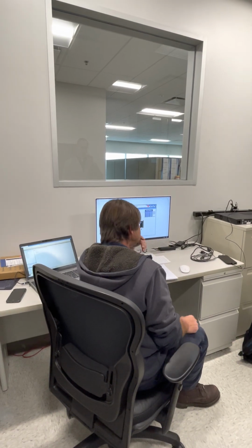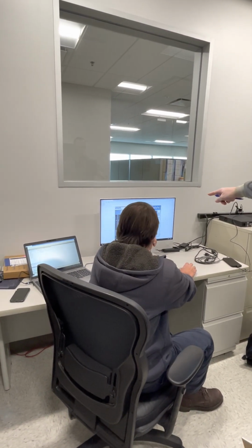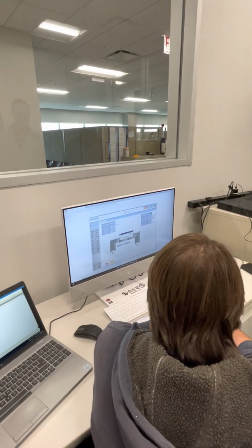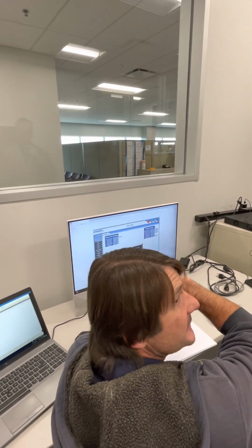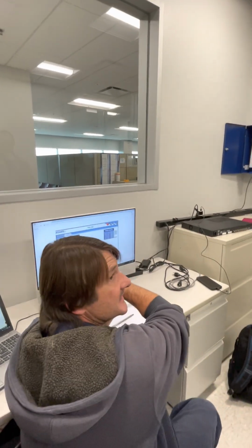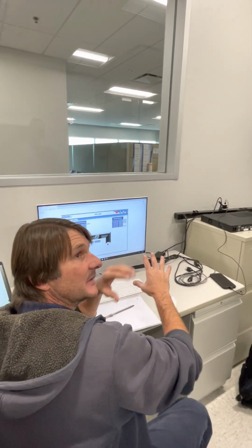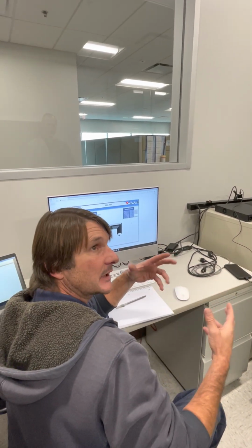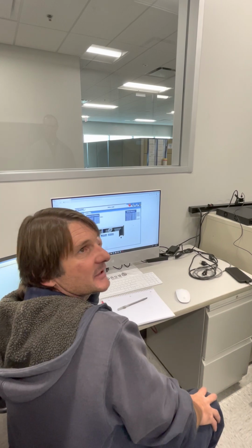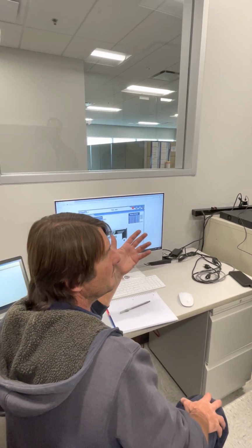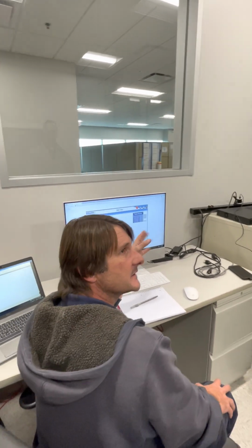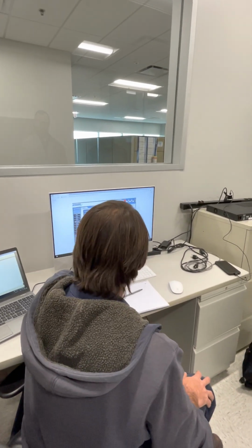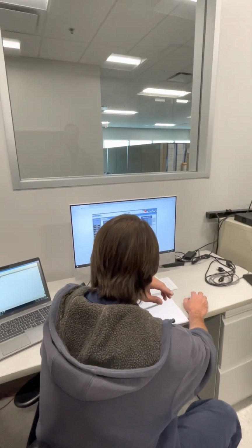Yeah, makes sense. So now, does this show it on the unit and give us an email? This is not going to be on the unit. This is not part of the thermostats. This is part of your automation system. This is where the management of the BAS system comes in. Basically, we grab things and then this is how we generate alarms, because the thermostats can't generate alarms. They got some basics in there, but nothing temp based or anything that's going to alert you to it. That's why we try to do an email when there is an alarm.